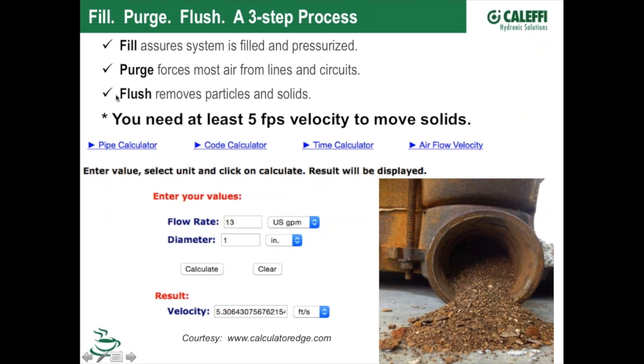The third part that sometimes gets overlooked is what I call the flush portion of the fill and purge. And with the flush, how that differs from the purge is I want a little bit more velocity. An example here, here's a boiler that somebody's taken out of a job, and you can see they've laid it outside, dumped out that debris that's in it. Filling and purging a system doesn't necessarily move this type of particle out.